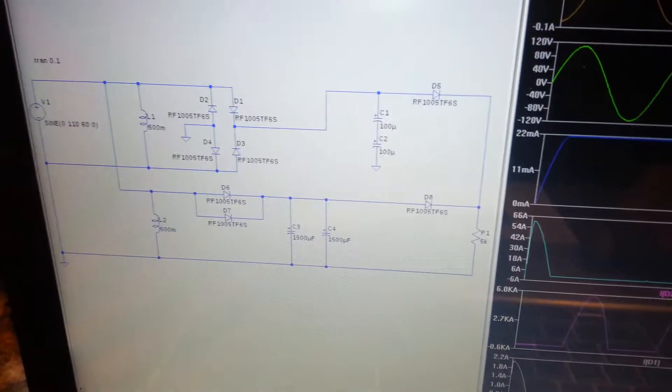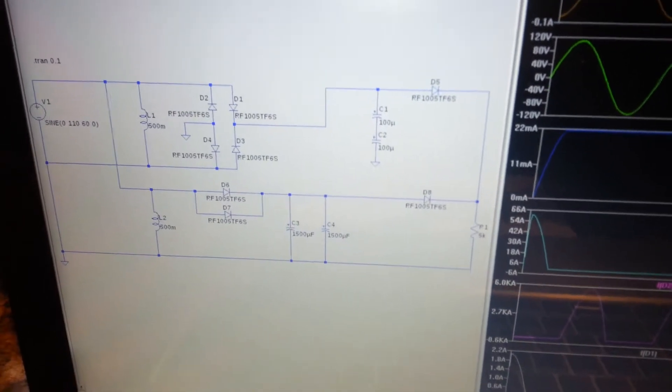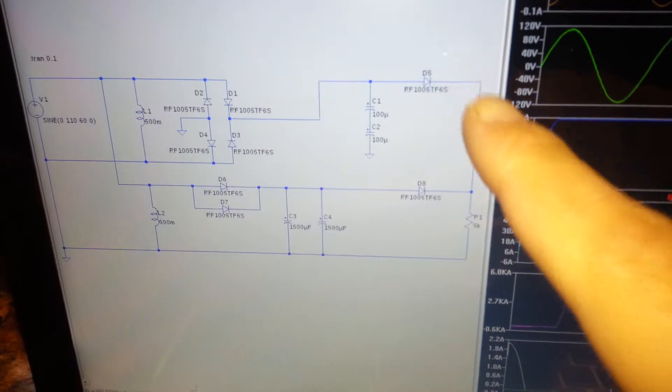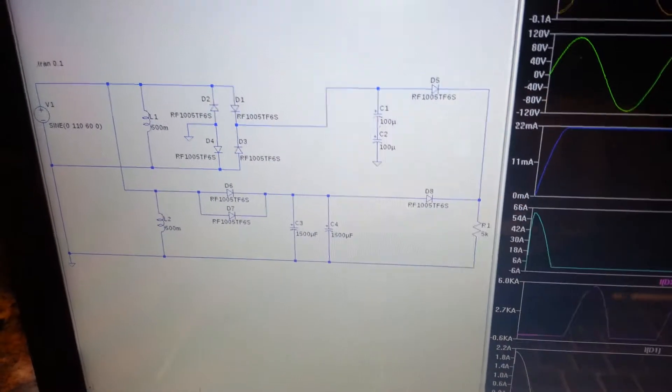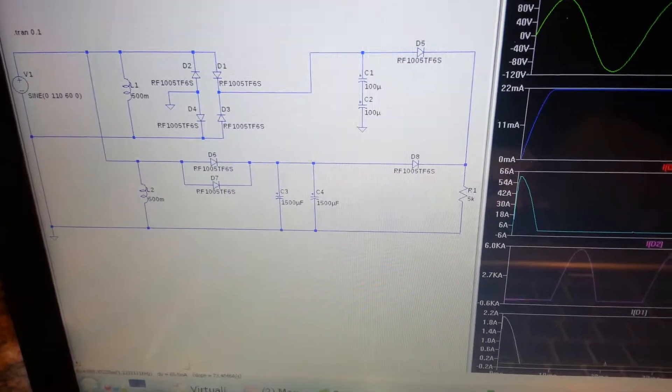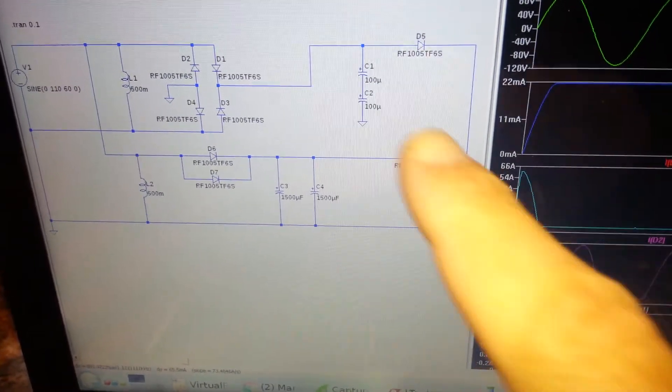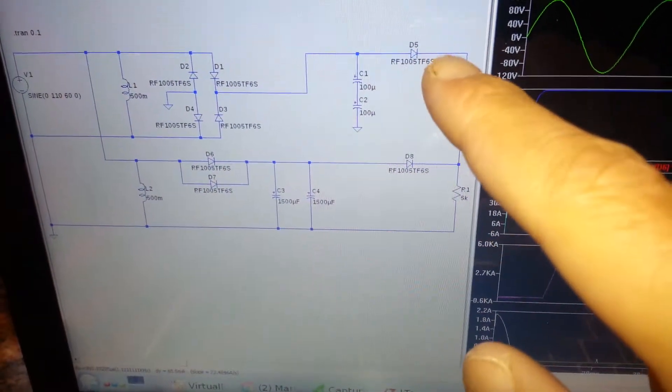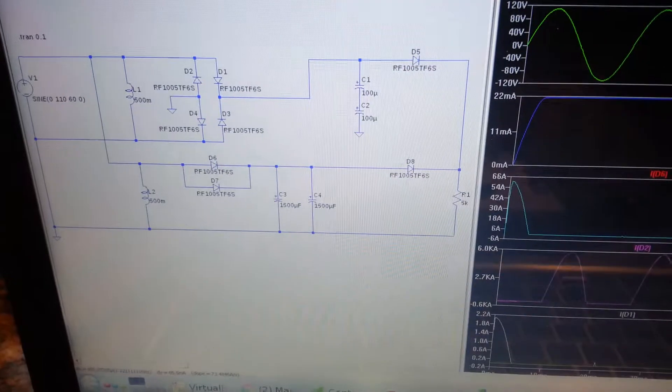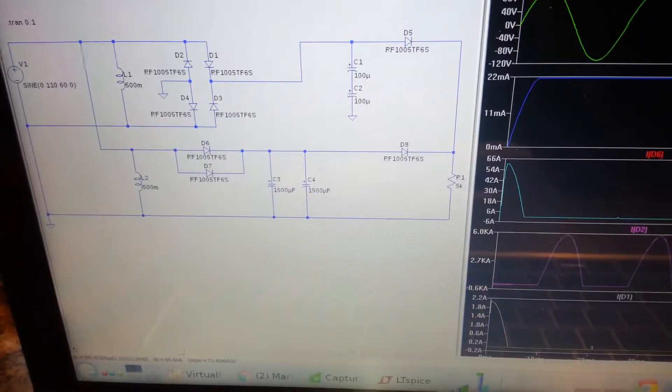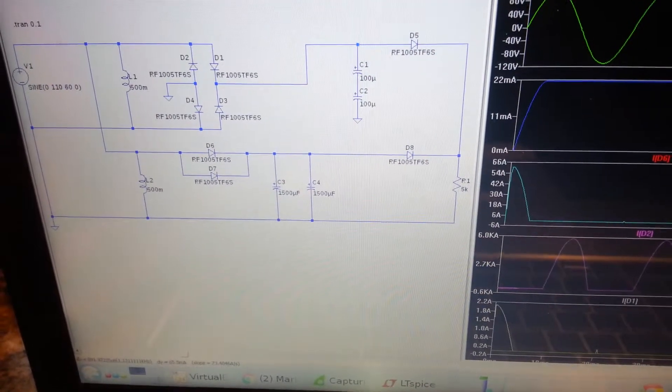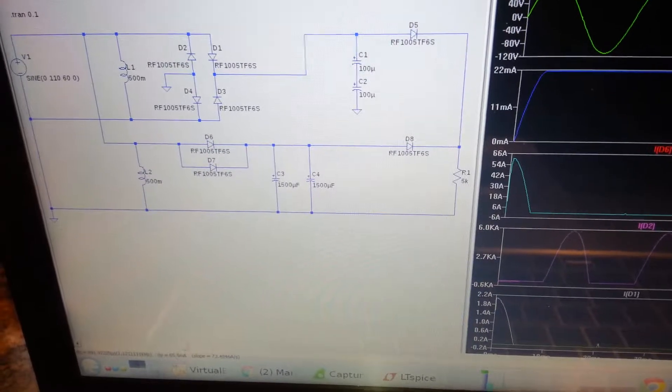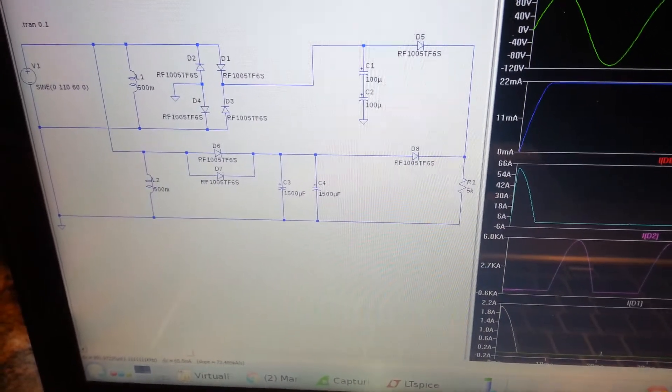That explains the humming, but what it does not explain to me is why I had some damage to the signal processing board in the dual diode box. Maybe part of that large short-circuit current found its way past this diode, past this rectifier, into the box, and somehow was flowing through that current sensor resistor, causing the solder joint to overheat and melt. And that is the prevailing hypothesis right now.